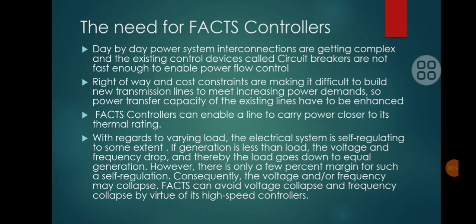Using FACTS controllers, we can enable a line to carry power closer to its thermal ratings. Normally, in the absence of such high speed FACTS controllers, a transmission line carries power much less than its rated value because there is always a margin put in to meet a sudden rise of currents due to faulty conditions. Such faulty currents can be easily controlled in the presence of FACTS controllers, so we need not place any margin.